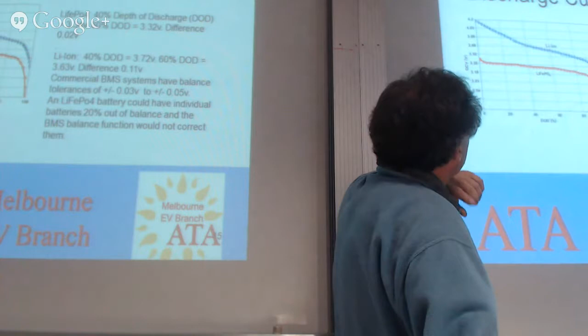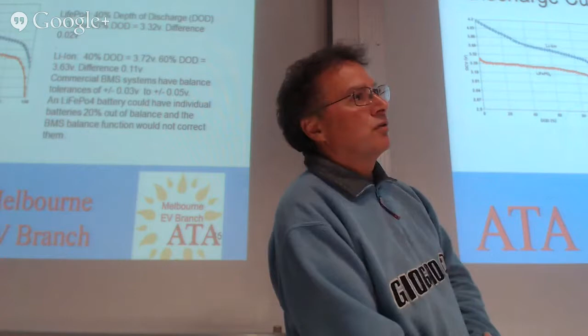But the reason that I've shown this curve is to talk about how the BMS operates on those. One of the most important functions of a battery is that it has to be kept in balance. Because if the battery's not in balance, if there's more charge in one cell than another, when you fully charge the battery, you're going to have problems of overcharging, and when you fully discharge it, you will have some cells that go flat. So the actual balance of the battery is extremely important in maintaining the life of the battery.